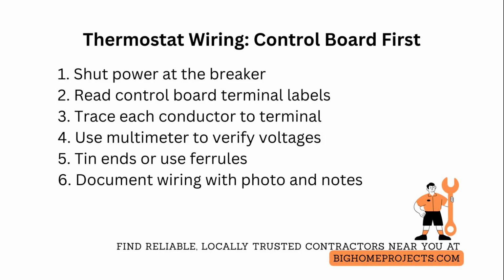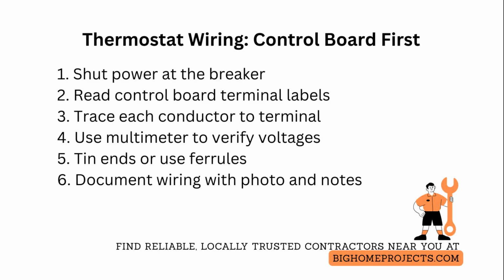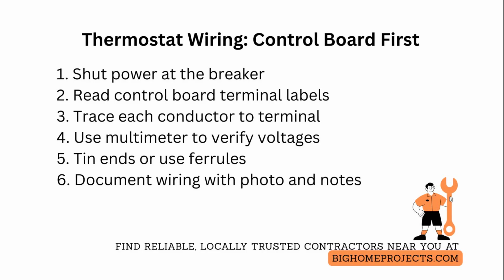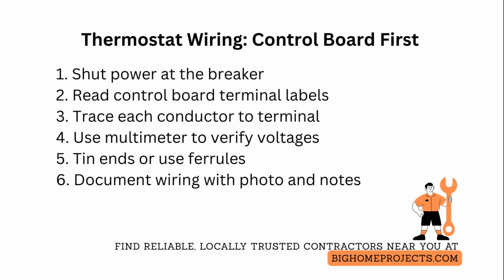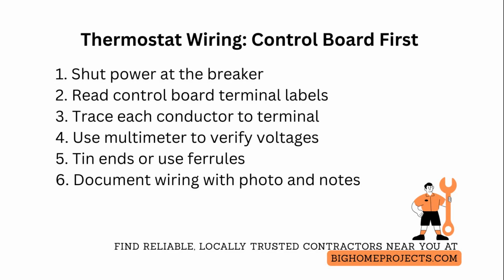For smart thermostats that require continuous power, confirm a stable, common connection on the control board, and if none exists, evaluate adding a common from the transformer or installing a separate 24-volt transformer kit while ensuring total transformer load remains within capacity. If the system has multiple transformers or zone controllers, isolate and identify which transformer feeds the thermostat circuit to prevent backfeeding. Use a continuity and voltage test between suspected common and R when calling for heat or cooling to see expected state changes.